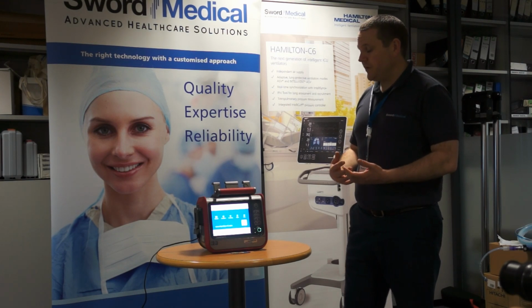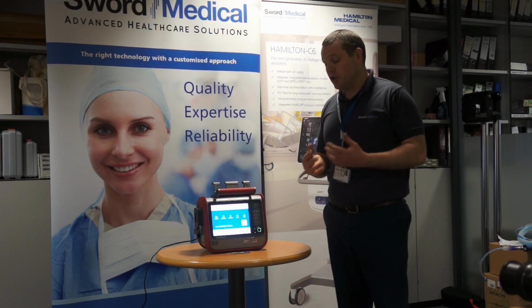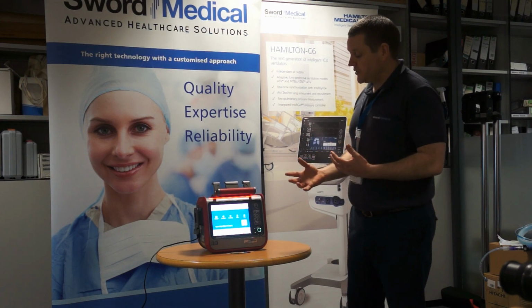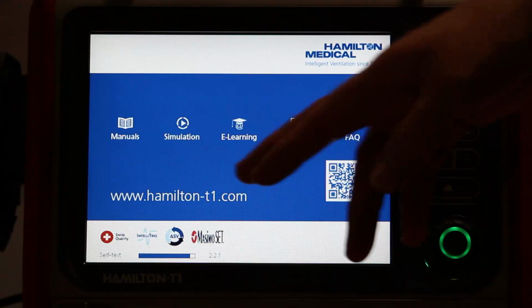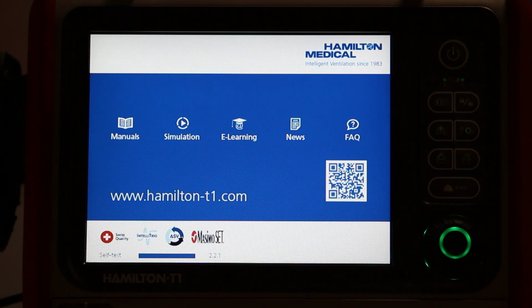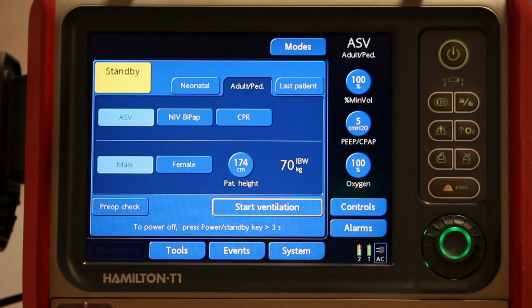So for that reason we would recommend that you leave the ventilator turned off when it's not in use. So whoever comes to it has to turn it on. It's running through the self-test, so you know the ventilator is good to go once it switches on. So when it's not in use, turned off and plugged in. So the ventilator now has switched itself on.